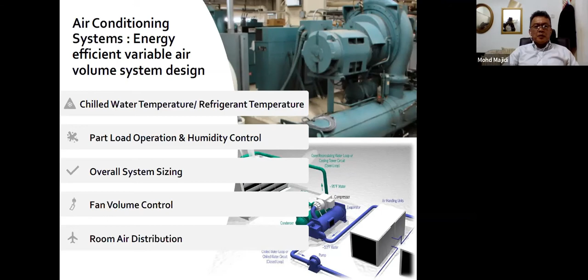For cooling systems, you need to reduce heat gain if possible. What are the control set points? What is your control strategy? Are manual overrides being done? Are windows being left open? Is the heating on at the same time? How are the occupants dressed - maybe some are too cold and have to wear gloves in the office. Don't be surprised, I've seen this in some buildings.